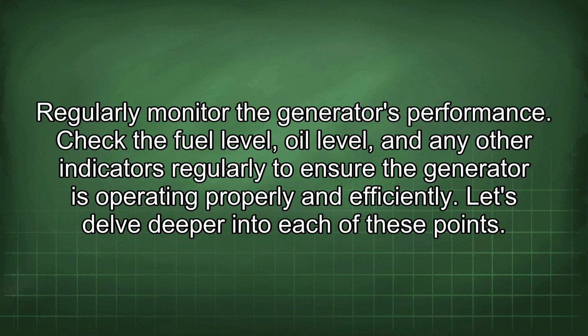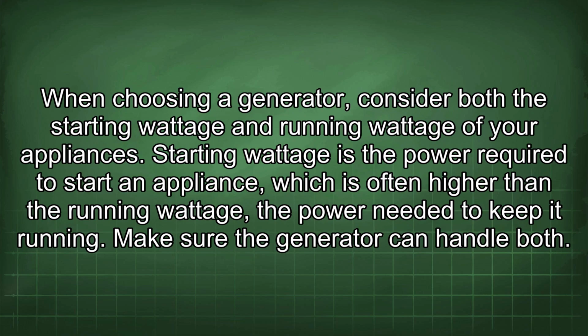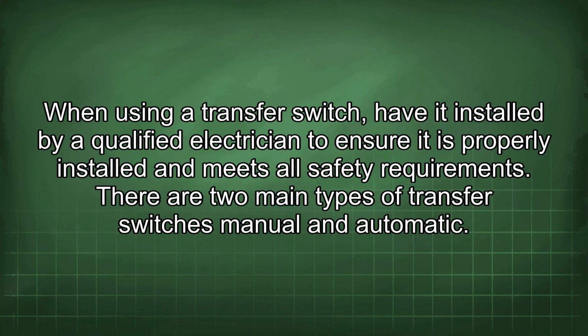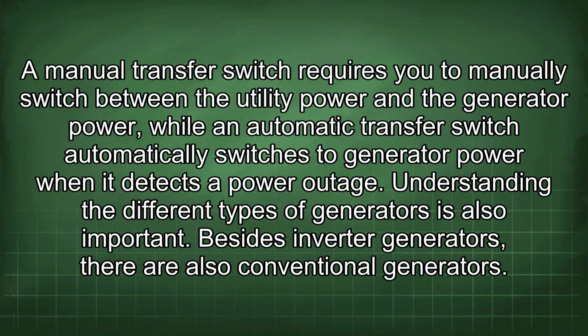Let's delve deeper into each of these points. When choosing a generator, consider both the starting wattage and running wattage of your appliances. Starting wattage is the power required to start an appliance, which is often higher than the running wattage, the power needed to keep it running. Make sure the generator can handle both. When using a transfer switch, have it installed by a qualified electrician to ensure it is properly installed and meets all safety requirements. There are two main types of transfer switches: manual and automatic. A manual transfer switch requires you to manually switch between the utility power and the generator power, while an automatic transfer switch automatically switches to generator power when it detects a power outage.